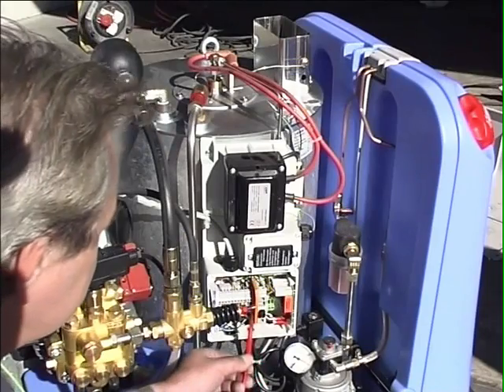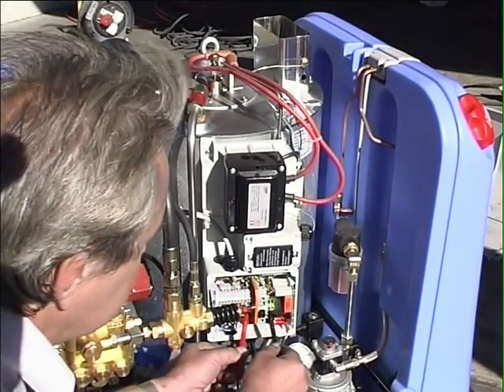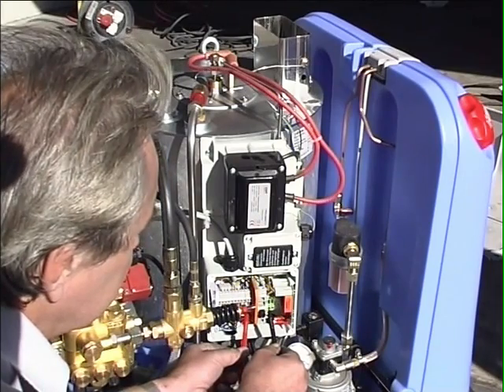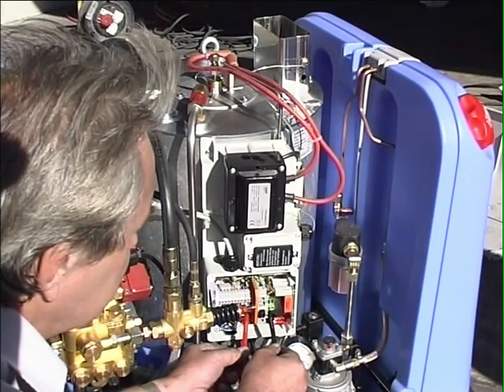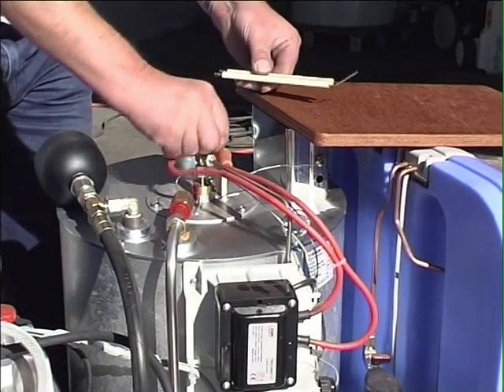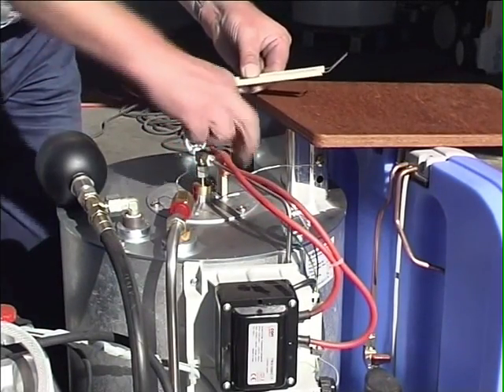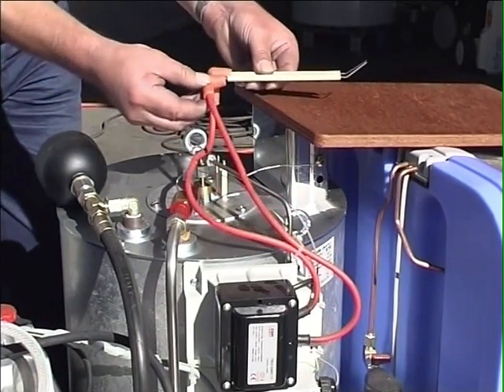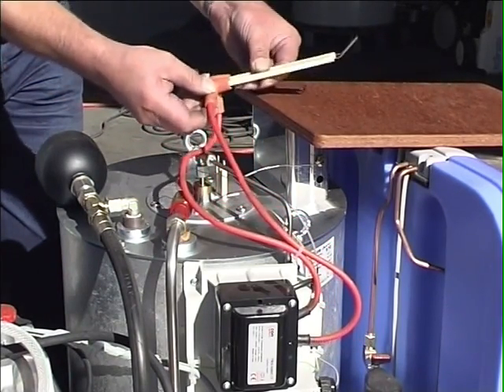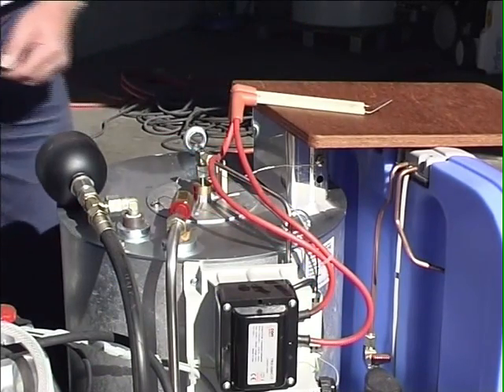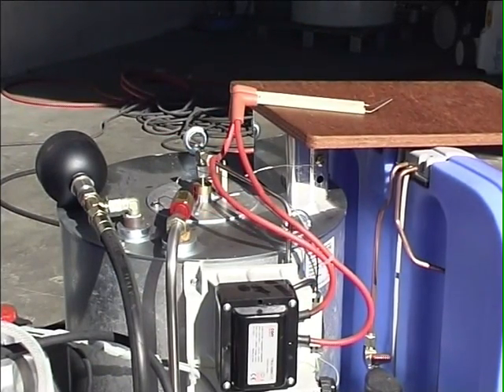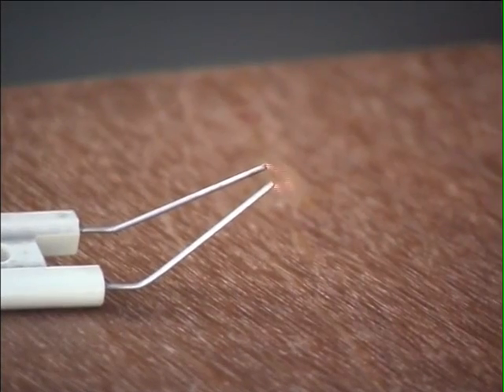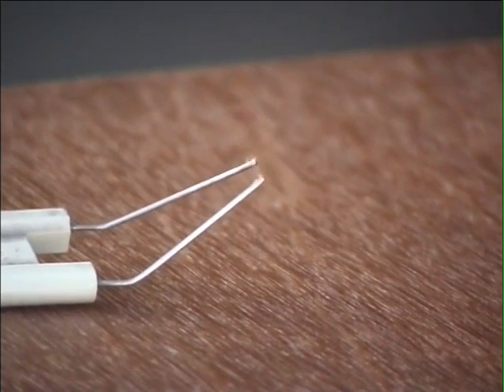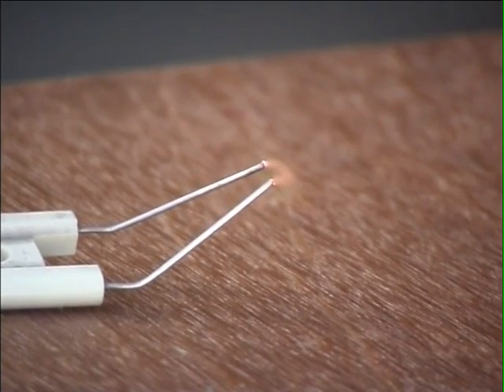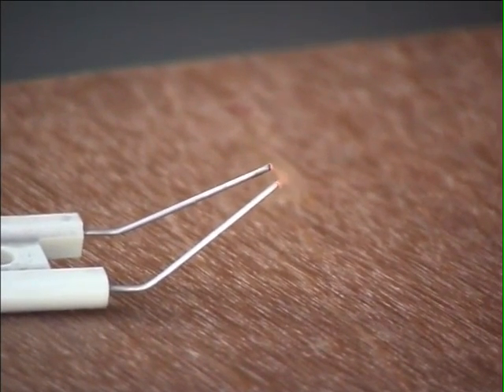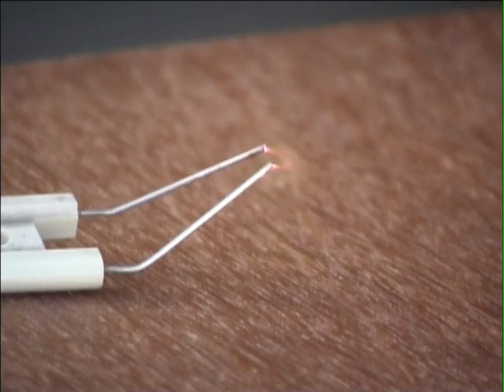Determine the voltage on the ignition transformer for the O series via terminals 2 and 11, and via terminals 15 and 18 for the 5 series. If there is a voltage, switch the machine off prior to the next step. Remove the plug from the electrode and connect it directly to an external ignition electrode. You must place it on a safe isolation. Now you can briefly switch on the machine, but pay attention, do not touch the ignition electrode. If the electrode functions, the ignition transformer and ignition are okay.